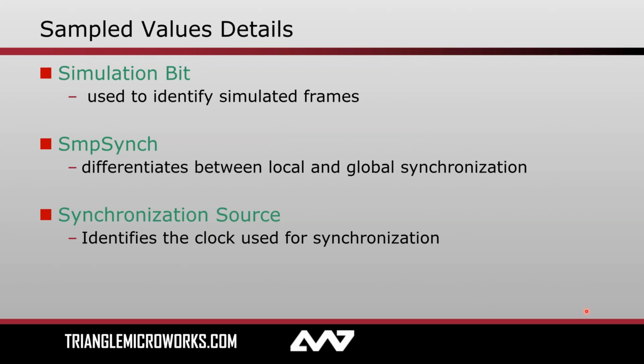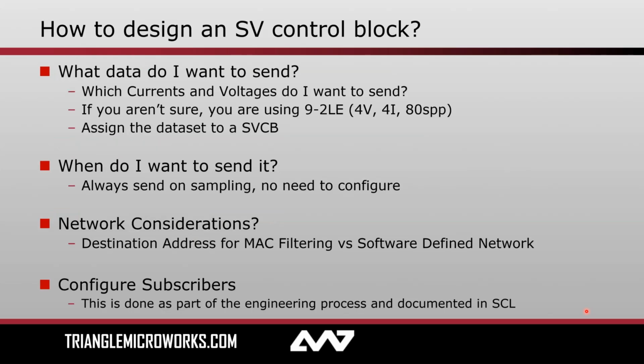I talked about how time synchronization becomes very important. We use PTP, Precision Time Protocol clocks, very accurate clocks, in order to synchronize all our devices so that we know they're publishing in sync with one another. SMP sync allows us to specify if a particular message was synchronized to a local clock on the device or to a global synchronization source like one of these PTP clocks. It's common to have multiple PTP clocks for the sake of redundancy. We refer to these as grandmasters. So you might have multiple grandmasters, in which case the synchronization source can be used to identify which grandmaster you were synced to at a certain time. Again, these aren't necessarily considerations you'll have to keep in mind when you're actually designing a sample value control block, but I wanted you to be aware of them.